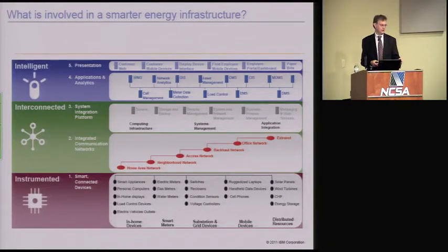Operational information would be: the power's on, the power's off, this is the voltage coming in, this is the voltage going out. Non-operational information, in switchgear for example, might be: how many milliseconds did it take the contacts to open and close? What was the length of the arc when you opened a 300 amp circuit? All of this helps maintenance people understand what's going on in the equipment as it works. This is very valuable to utilities in maintaining a high level of operational excellence.